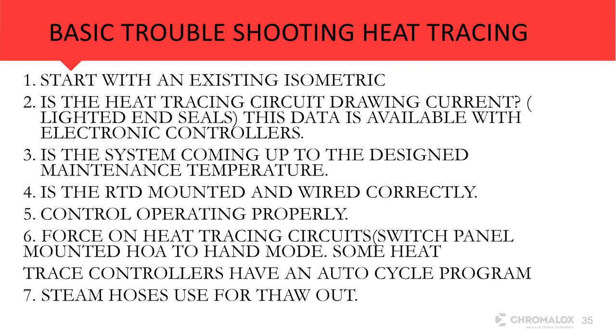I talked about steam hoses used for thaw out. One of the issues with that is that you will damage the conductive core of the heat tracing cable if you put too much steam on the wrong cable. So make sure you understand that. That happens a lot, and a lot of times the conductive cores get destroyed, and then that section of the heat tracing is not working, and we end up with another issue in terms of heat tracing.